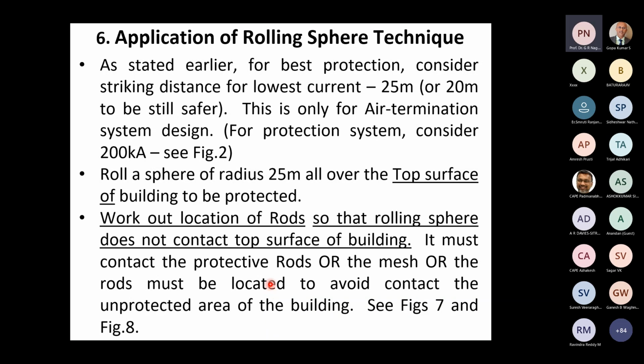Now, as I told you earlier, for best protection, consider the striking distance for the lowest current, typically 5 kiloamperes. For 5 kiloamperes, in the table I gave you earlier, for constants 10 and 0.6, the value came as 26 meters. So round it off to 25 meters, that's safer. Or if you want to be still safer, use 20 meters as the conical area. Now this is only for air termination system design. For protection systems, we have to consider in a different way altogether. That's the protection system within the building, how to protect the electronics, electricals, etc.